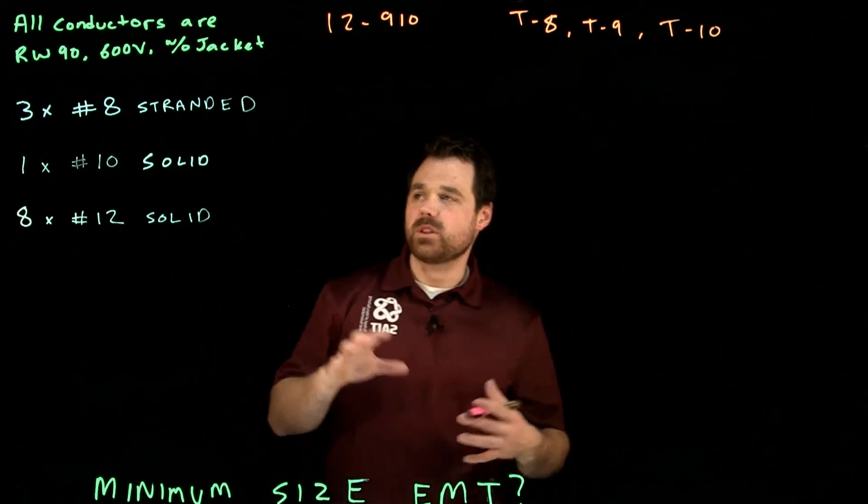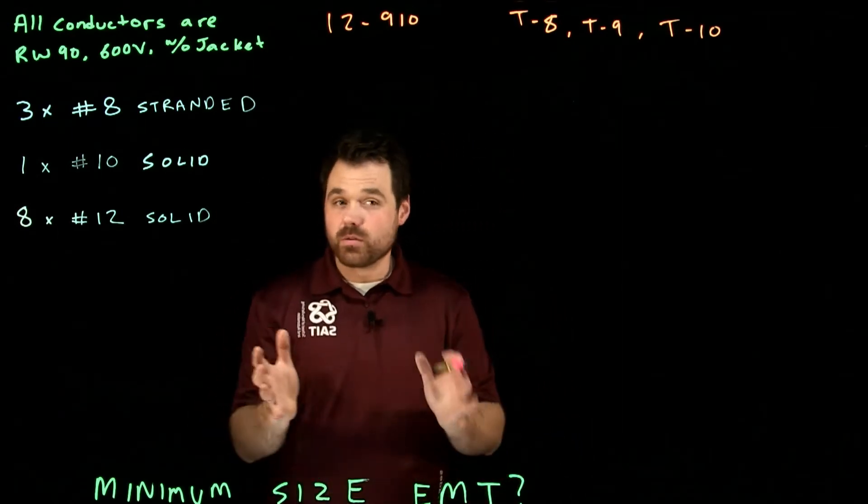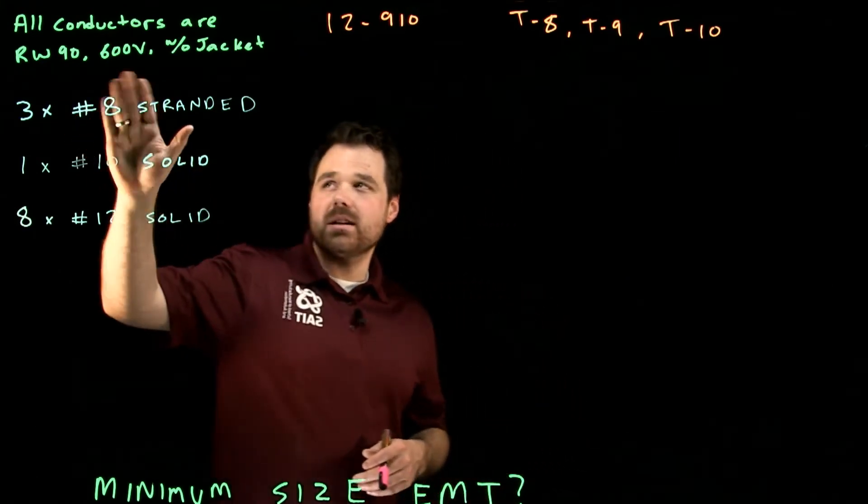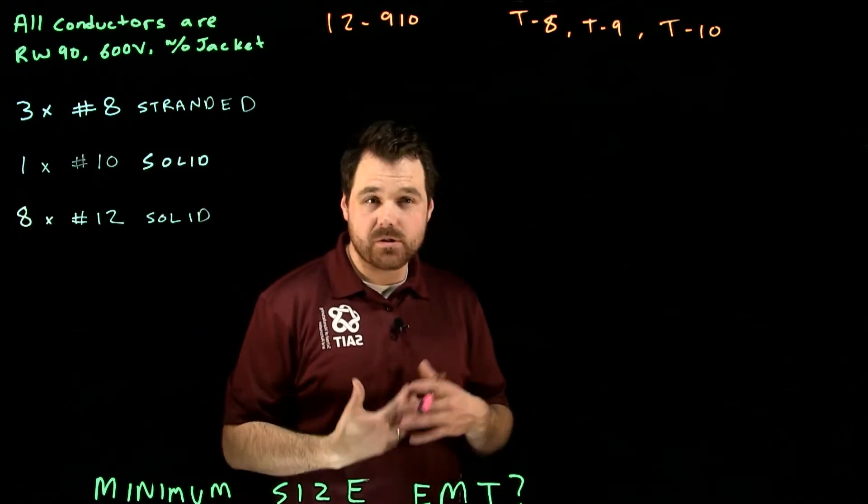So our first step with these is I need to go to table 10, A through D and figure out how big each of these conductors are. So we know they're RW90, 600 volt without jacket, but we have some stranded conductors and some solid conductors.